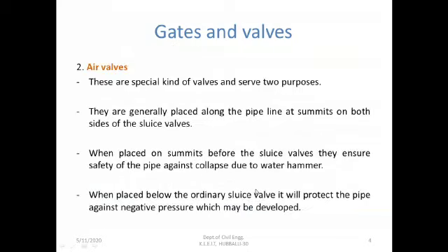Now, why are they being provided at those two places? At the upper elevation, it is just to ensure the safety of the pipe against collapse due to water hammer. And if it is placed below the sluice valve, it is to protect the pipe against negative pressure.